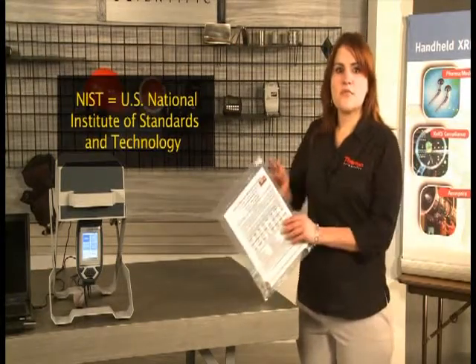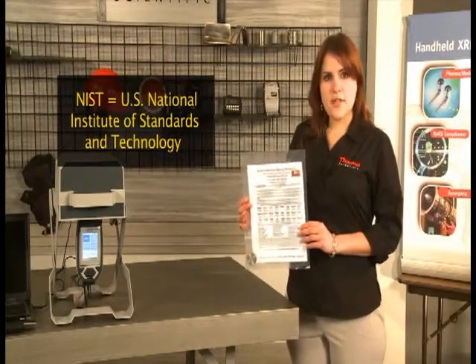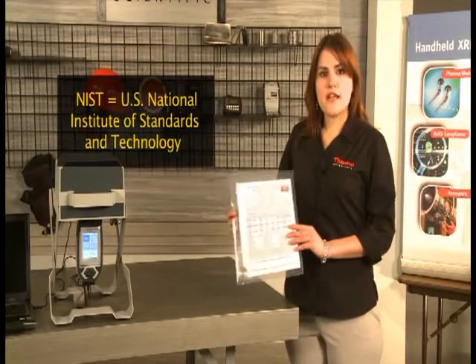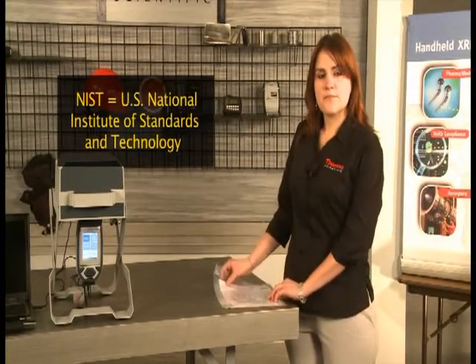Welcome to Module 2, Check Sample Measurement and Detector Calibration. Thermo Scientific Niton analyzers are capable of providing you with very high precision and accuracy. However, in order to maintain this precision and accuracy, you have an important role to fill. Your job is to verify that the instrument is performing properly on a routine basis. To enable you to do this, we supply a certified NIST traceable reference standard with your analyzer. This reference sample will help you verify the instrument is functioning properly.